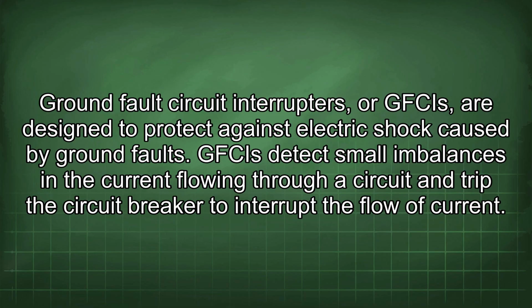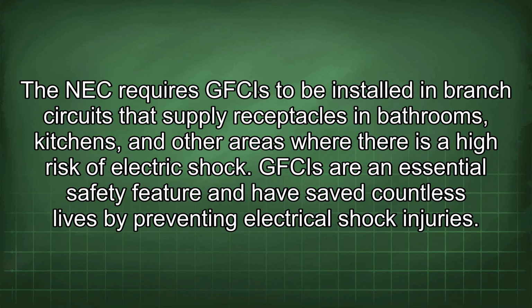Ground fault circuit interrupters, or GFCIs, are designed to protect against electric shock caused by ground faults. GFCIs detect small imbalances in the current flowing through a circuit and trip the circuit breaker to interrupt the flow of current. The NEC requires GFCIs to be installed in branch circuits that supply receptacles in bathrooms, kitchens, and other areas where there is a high risk of electric shock. GFCIs are an essential safety feature and have saved countless lives by preventing electrical shock injuries.